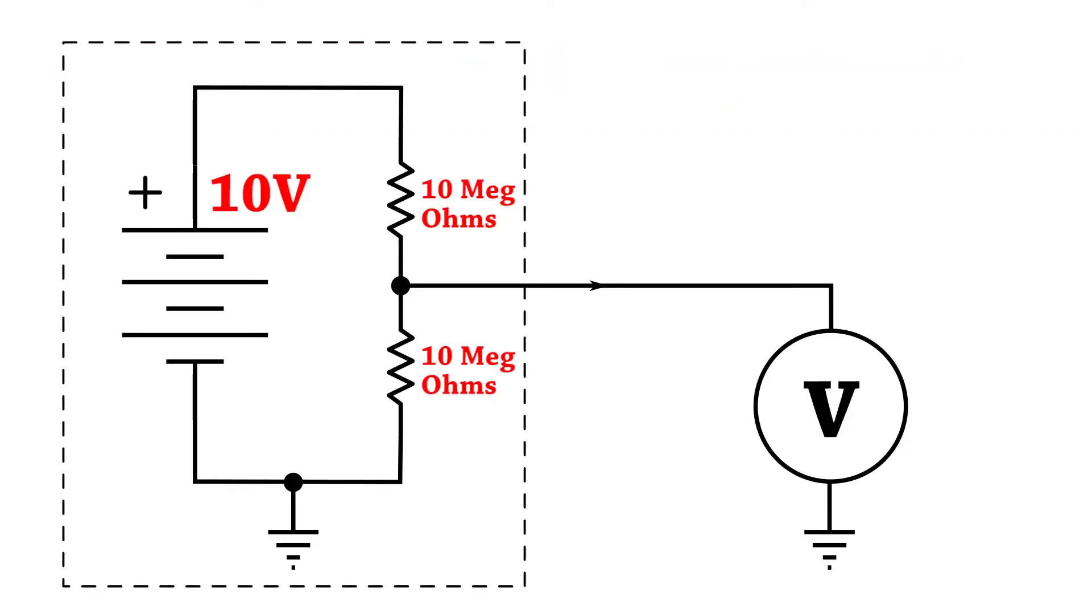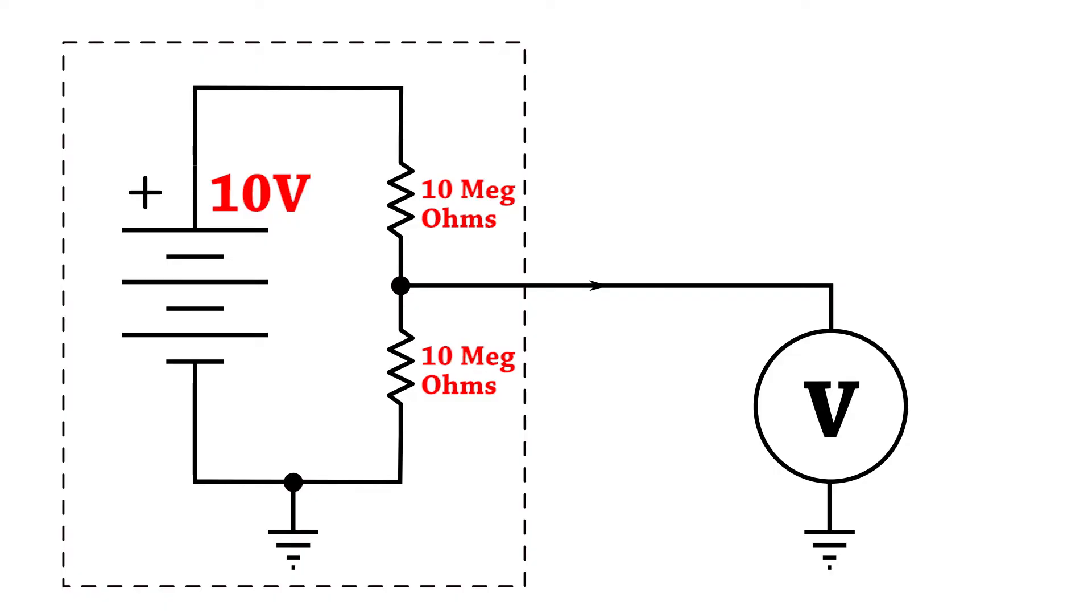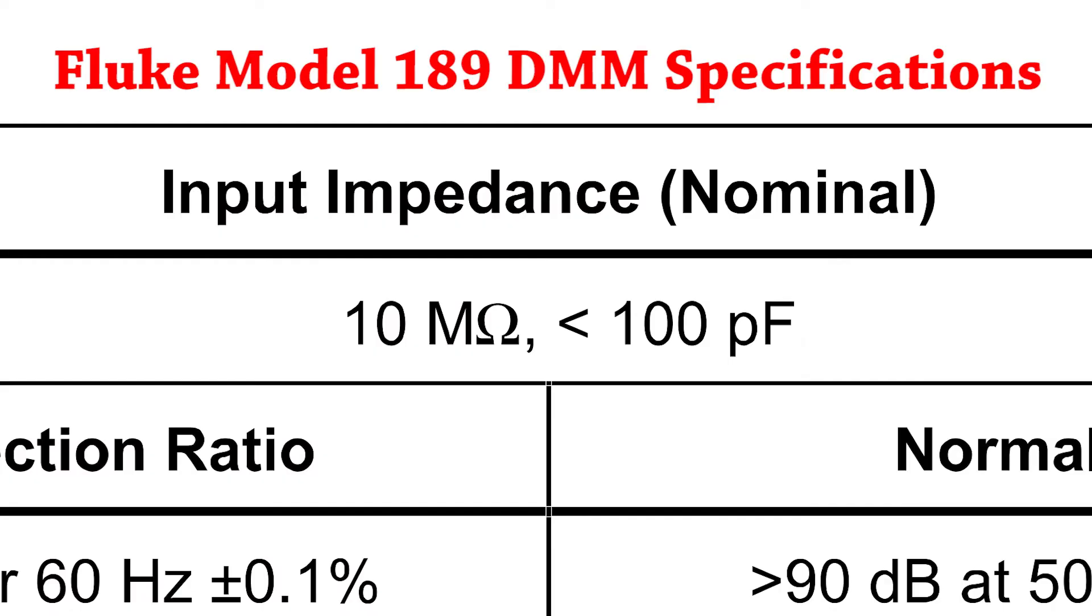To measure anything, you've got to sample some of it, and that means it's got to draw a tiny amount of current from the voltage you're measuring. If we look carefully at the specification sheet for our Fluke voltmeter, we can see that the input impedance is listed as 10 megaohms.